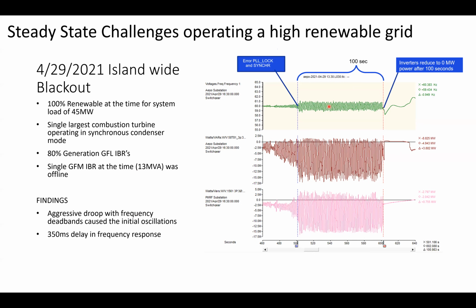The other thing that we found out as a result of this is at the time we were operating our grid following inverters with a very aggressive droop. It was at 0.8%. We've since increased that droop percent to 3% across the island on our fast frequency response. But that was one of the lessons learned there.